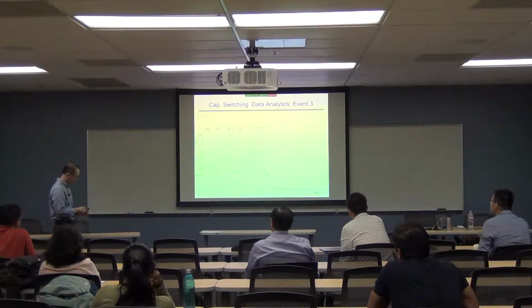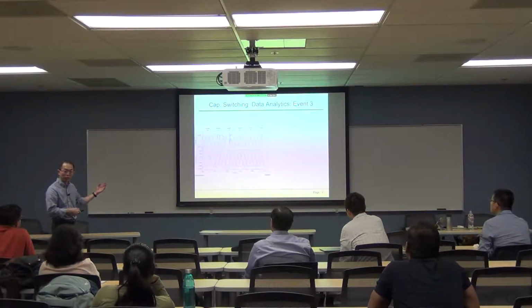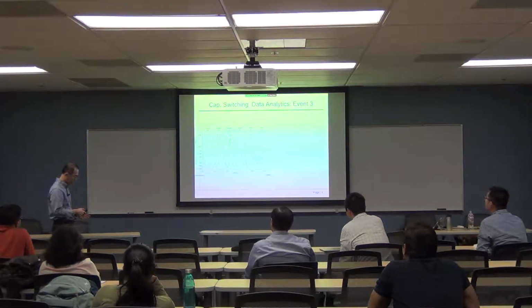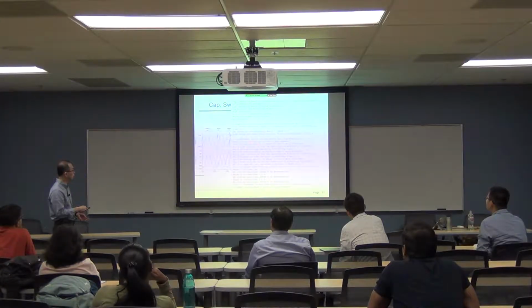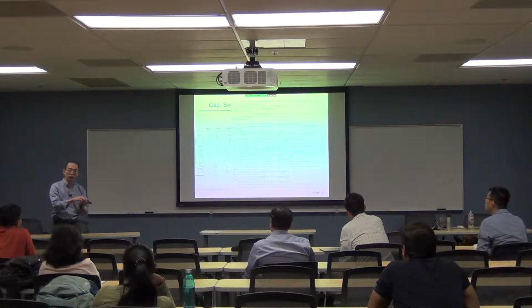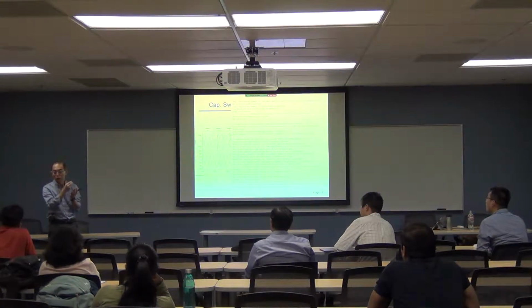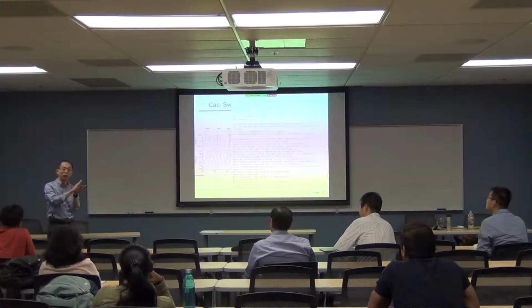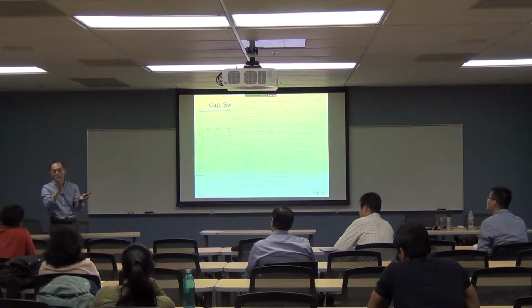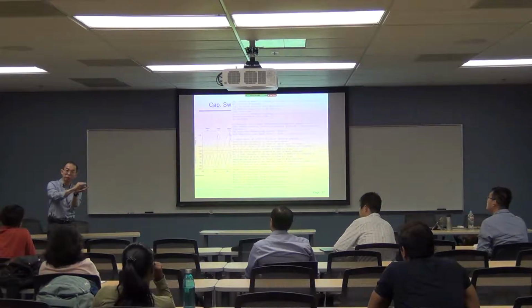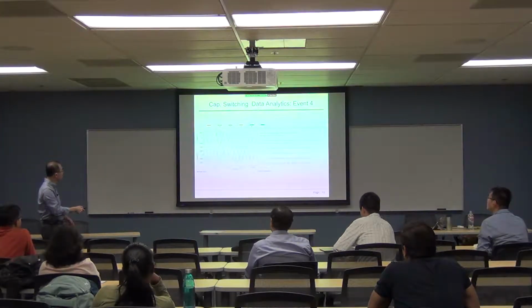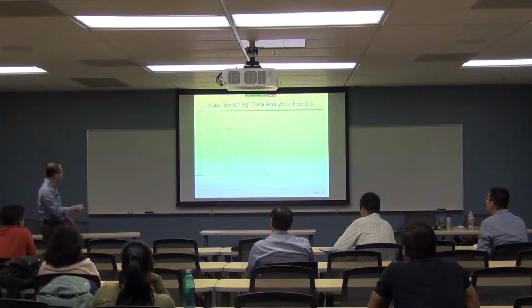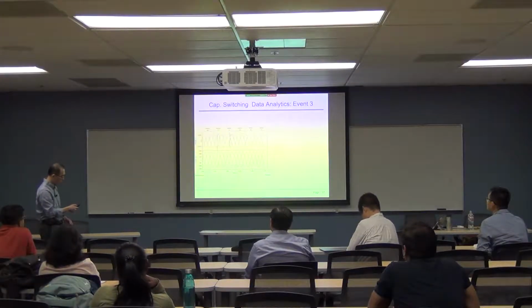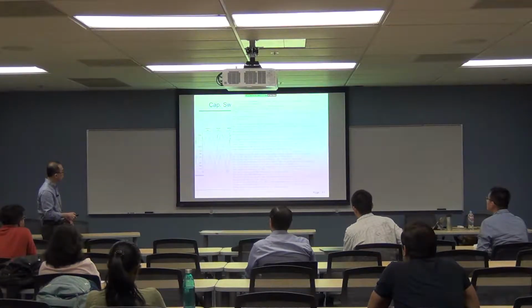Now the next thing is, what do you think of these waveforms? This is capacitor energizing, okay, capacitor energizing waveforms. And then you can see this one here has a restrike during opening. I can tell this is a restrike during opening because in this particular one the switch has already opened, but because of some contaminants on the blades, as it is moving opening, the arc, as it passes to zero crossing, the arc is extinguished, but as it approaches the peak voltage, the arc jumps across again. It doesn't mean the blade is doing this, it's simply that the arc is re-established. That's why you can see that right here near the peak. So the energizing waveform should not see this type of restrike.